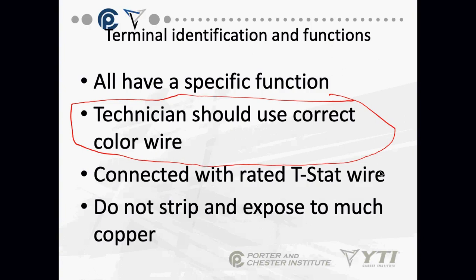Thermostats should be connected with rated thermostat wire. Again, there's specific thermostat wire out there on the market that you can buy from Home Cheapo and any of the other home improvement stores out there, but again, sometimes it's cheaper to buy it from your supply house. Thermostat wire always starts with the number 18 for 18 gauge wire, and then it's going to have a slash, and it's going to have another number like 6, 2 (don't ever use 2 anymore), 4, and it can go up to 12. So what this designation is saying is you have 18 gauge wire, and you have 6 wires inside the thermostat cable.